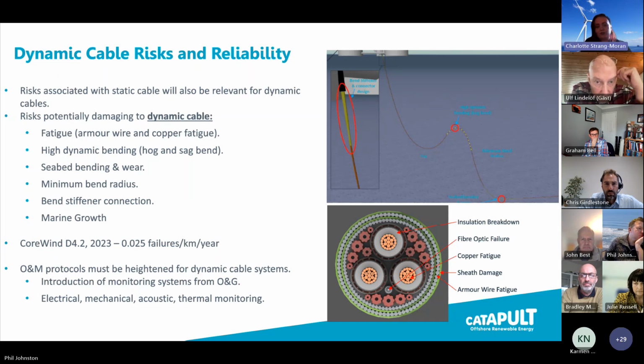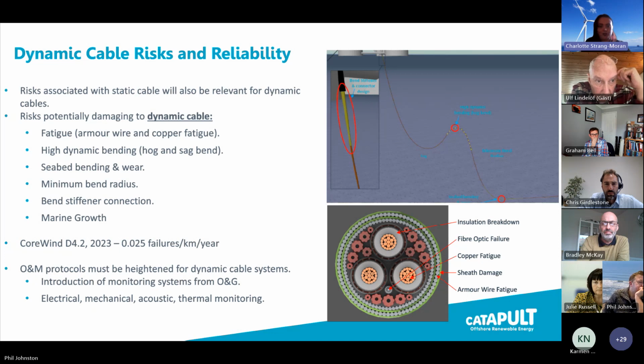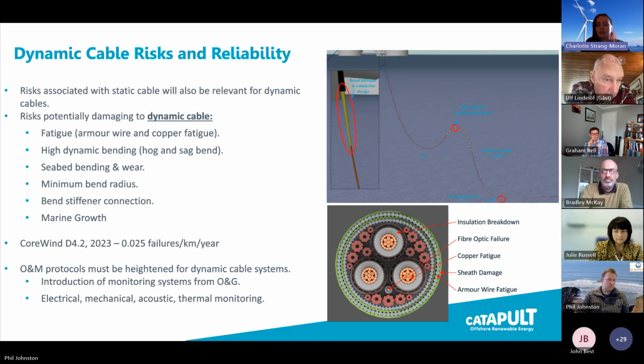So when we look at all of this, we need to realise that O&M protocols must be heightened for dynamic cable systems, with a requirement there as well to introduce monitoring systems. We can look at monitoring systems from other sectors, such as oil and gas, and we can also look at case studies from fixed wind sites as well, where a lot of fixed wind sites are introducing new monitoring technologies. But we should be looking at monitoring across your electrical aspects of your cable, mechanical, acoustic for any sort of third-party damages, and thermal monitoring as well.